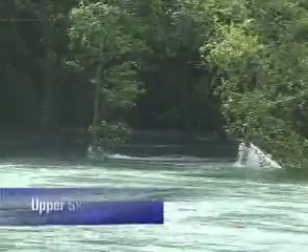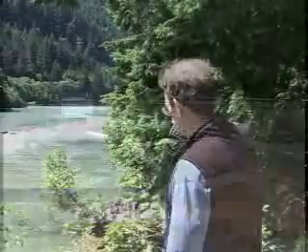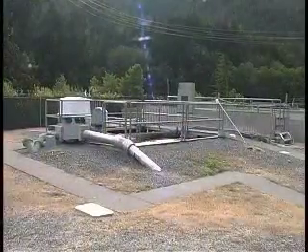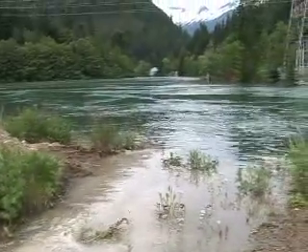But the water could only be raised so far to help flush the rocks downstream to deeper water. That's because the old sewage treatment plant in the little town of Diablo sits low and is subject to flooding. The problem is leaky sewage pipes — when the river level comes up, it raises the groundwater level, which comes over the top of the sewage pipes. That water goes into the pipes, gets pumped to the plant, and causes an overload. So basically, it was the capacity of the sewage treatment plant that was controlling when they had to stop.